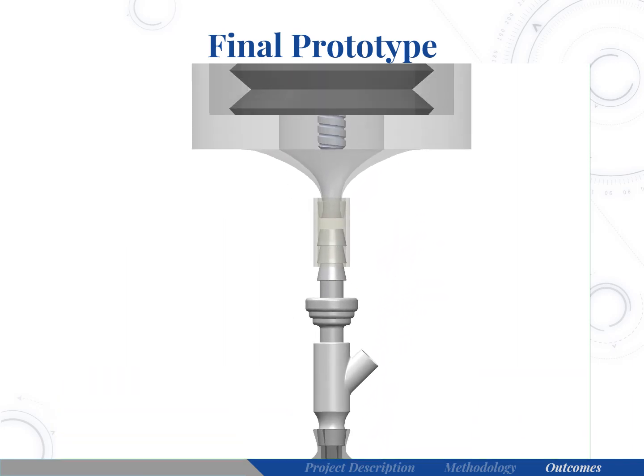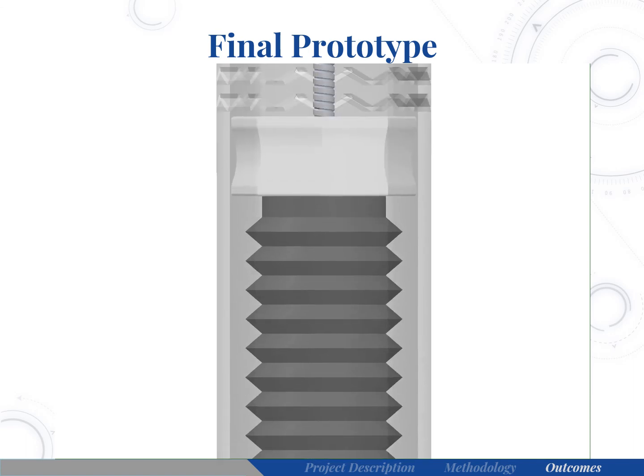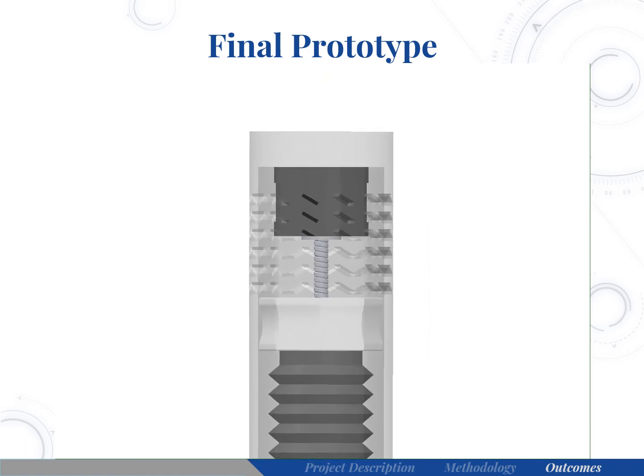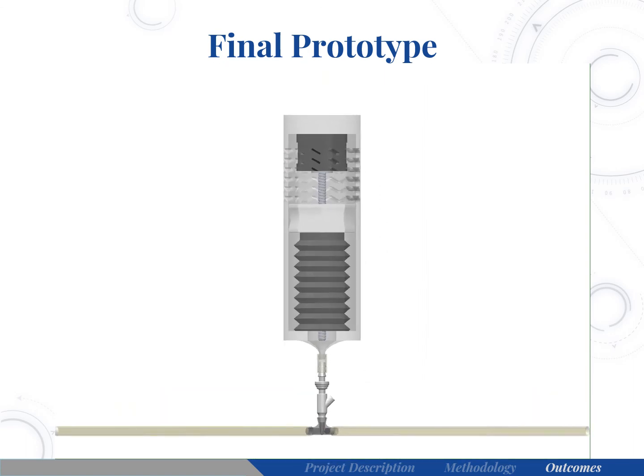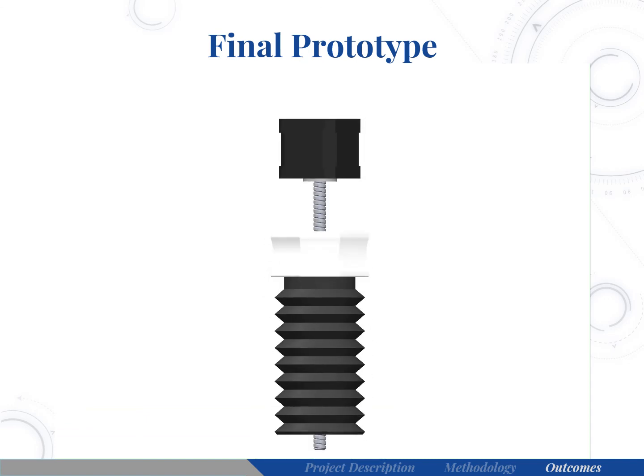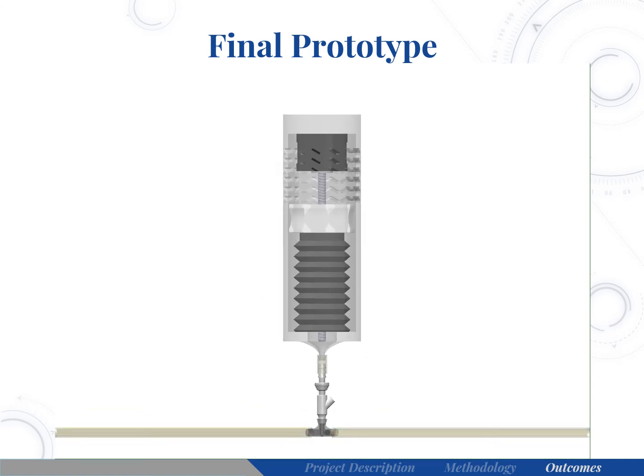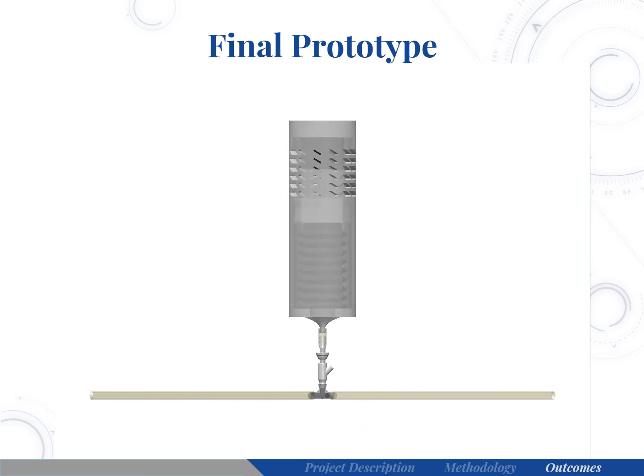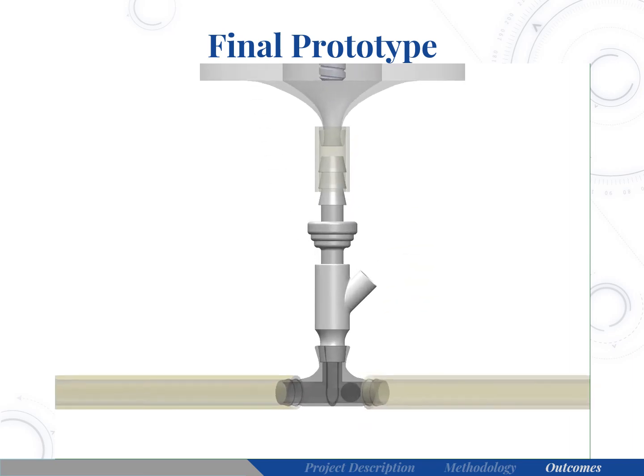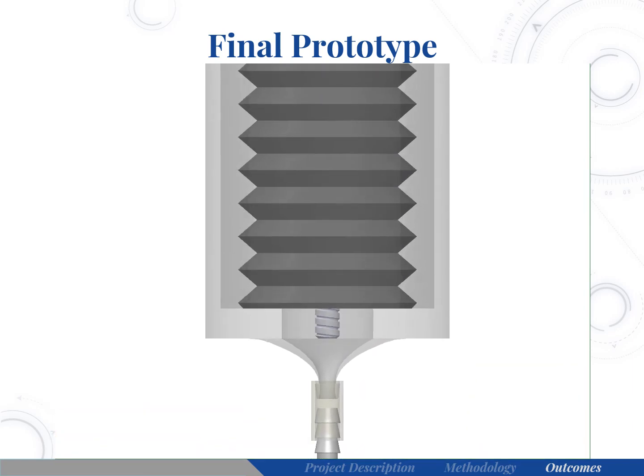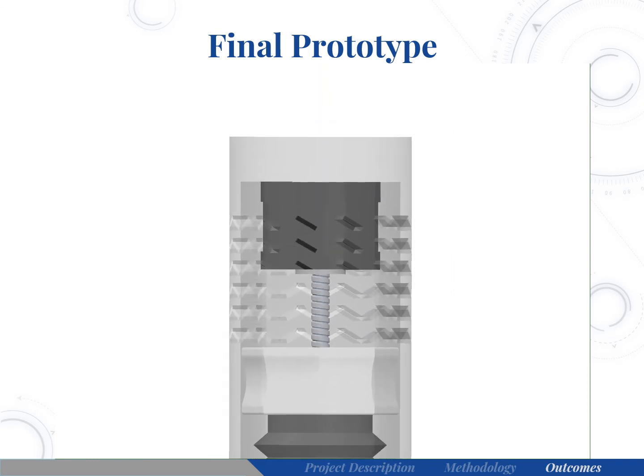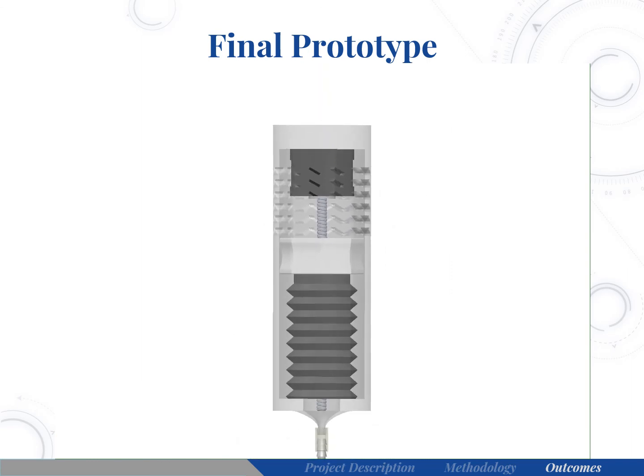When the bellows ejects air, the ball check valve will prevent back pressure from reaching the bladder and ensure fluids move distally towards the collection bag. The motor will then reverse, causing the valves to reverse, sealing the bellows component, and allowing the bellows to draw in sterile air through the vented compartments in the shell and subsequently through the one-way flapper valve housed inside the white compressor.